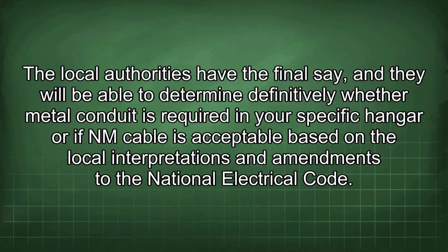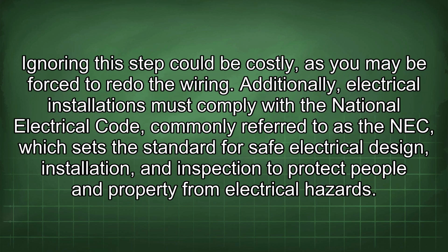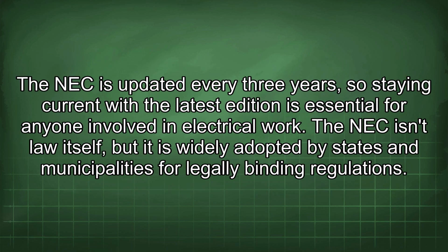The local authorities have the final say, and they will be able to determine definitively whether metal conduit is required in your specific hangar or if NM cable is acceptable based on the local interpretations and amendments to the National Electrical Code. Ignoring this step could be costly, as you may be forced to redo the wiring. Additionally, electrical installations must comply with the National Electrical Code, commonly referred to as the NEC, which sets the standard for safe electrical design, installation, and inspection to protect people and property from electrical hazards. The NEC is updated every 3 years, so staying current with the latest edition is essential for anyone involved in electrical work. The NEC isn't law itself, but it is widely adopted by states and municipalities for legally binding regulations.